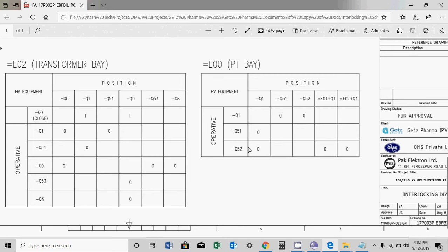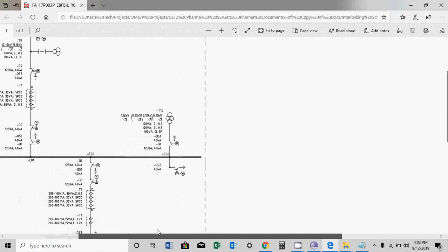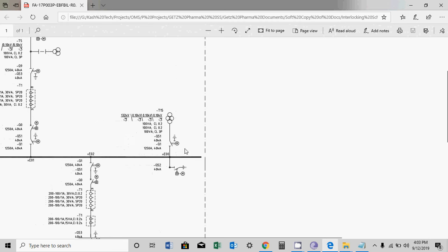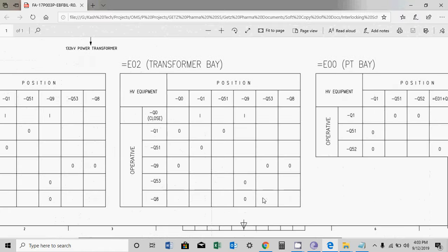So you can operate Q1 if Q51 and Q52 are open. Let's see what is Q51 and what is Q52. Q53 is the bus bar earth switch, which should be open. And Q51 is the earth switch which is built into Q1. For the earth switch, you have to open it first, and Q53 has to be open. Then you can close Q1. So this is the interlock table for this.